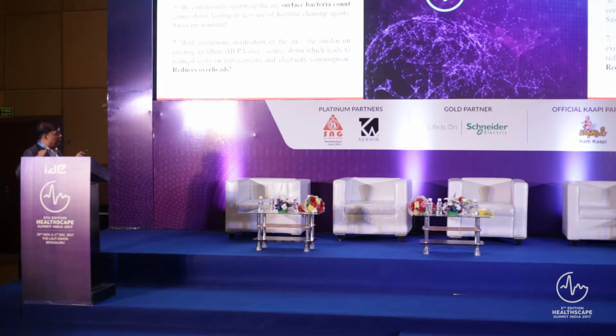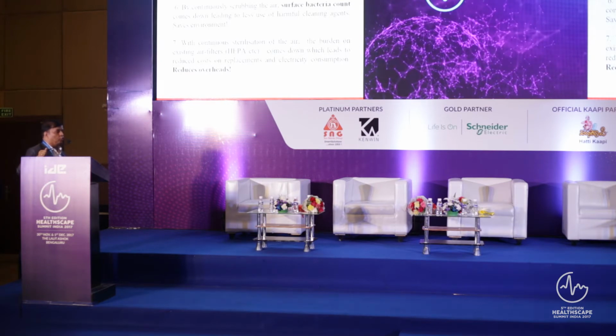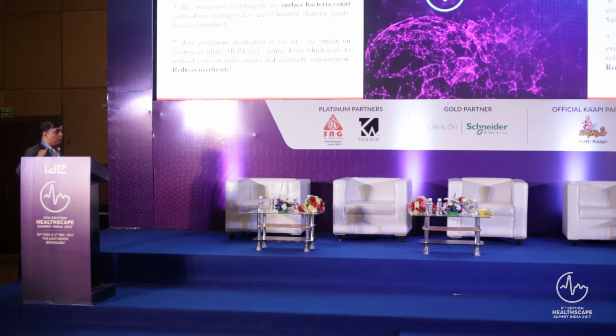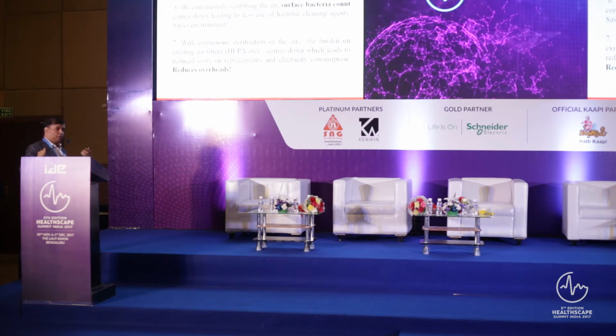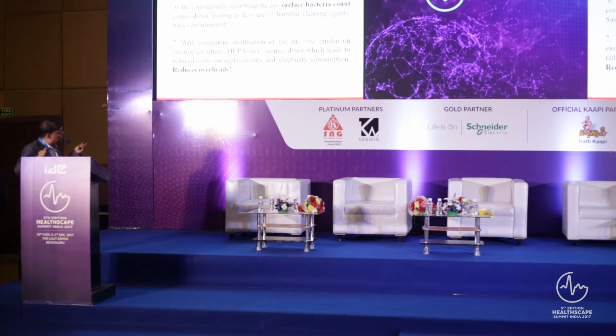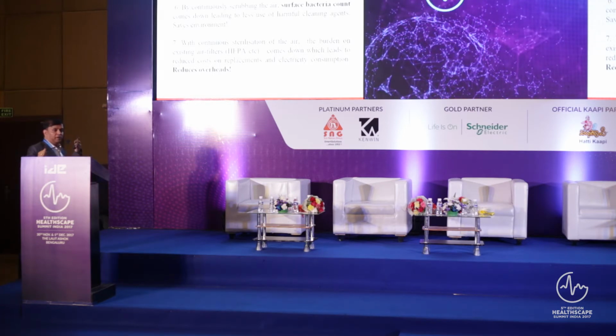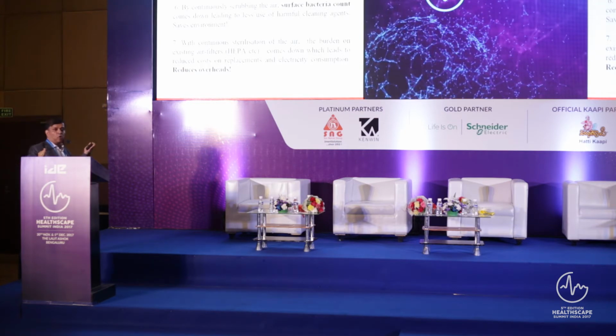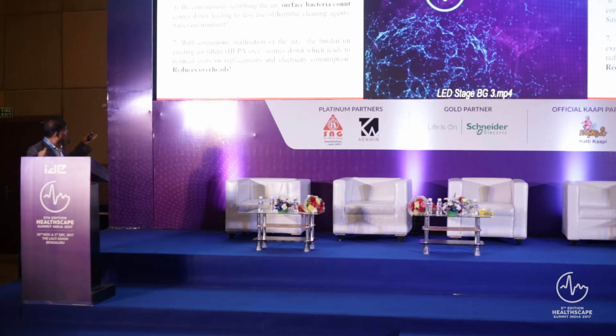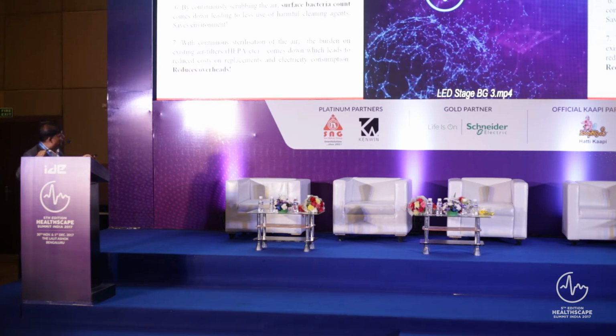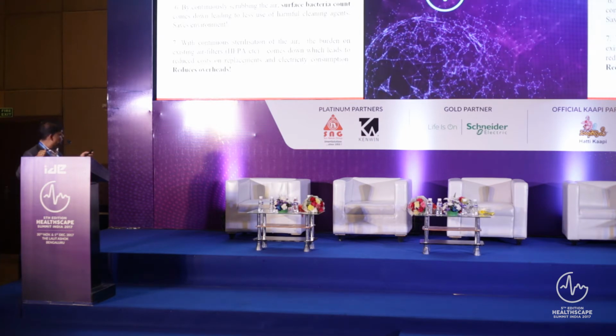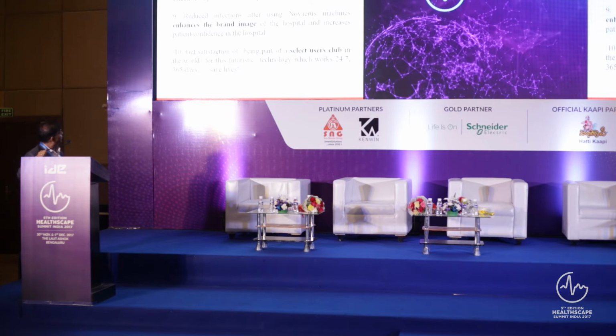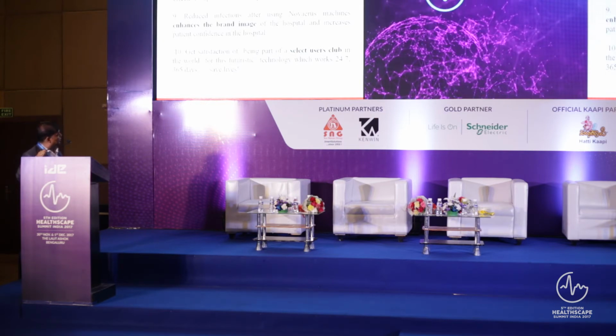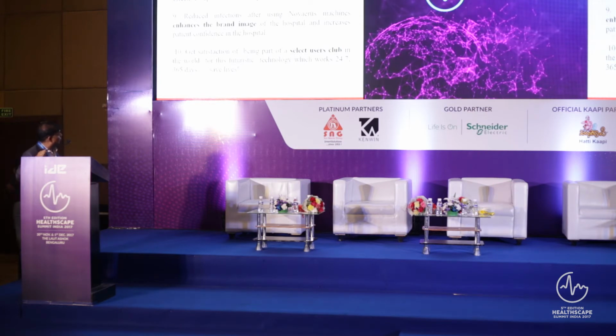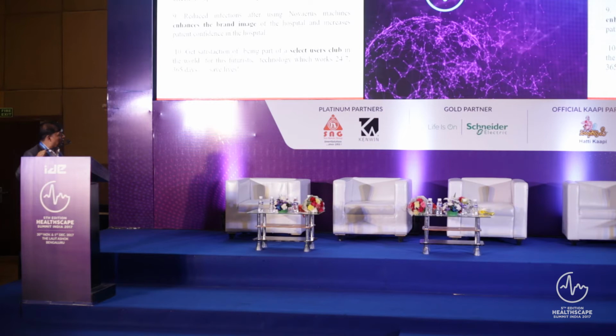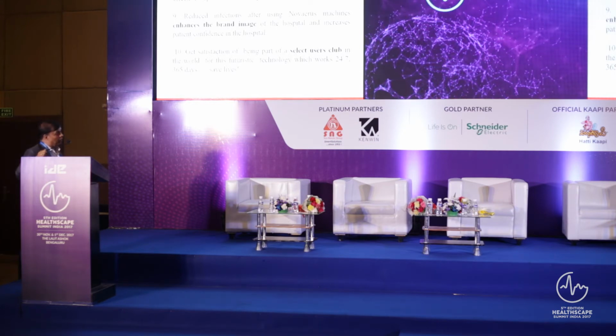Almost 68% of the surface bacterial count comes down because of cleaning the air with this technology, and we have the documents which I can share with you. Then with continuous sterilization of the air, there is another aspect. All of you are using HEPA filters in the duct system, and you need to change them, or you need to use a lot of energy to filter the air through that. This technology, if you are using it in the rooms, reduces the burden on your HEPA filter. It can allow you to have fewer air changes per hour because it adds its own equivalent air changes. So the cost of filter replacement comes down, the cost of electricity consumption comes down, so of course it reduces your overheads. And it protects and saves the life of not just the patient, but the doctors, nursing staff and visitors are also protected. So it effectively controls the spread of airborne infections, and when we are talking about TB, it is a very right step in that direction.